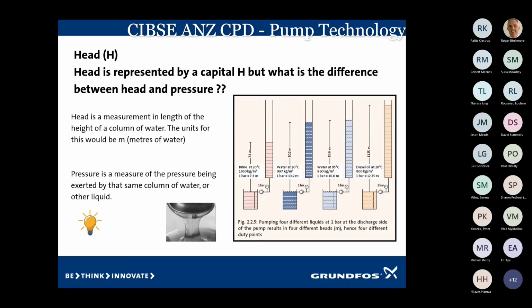That pressure gauge is reading 1 bar. If we climbed up a ladder, up a vertical pipe, you'd find that the water would be sitting at about 10.2 meters. Now, if I compare that with brine, which I'm pumping now, the pink one beside it on the left-hand side, the gauge is still reading 1 bar at the pump, but now I'm only producing 7.3 meters. Because if you have a look at the density, it's now 1.3. It's moved.